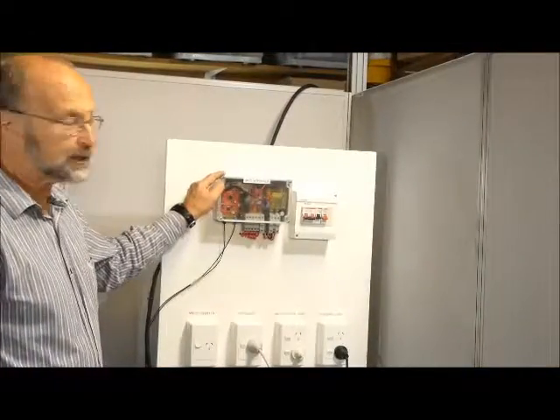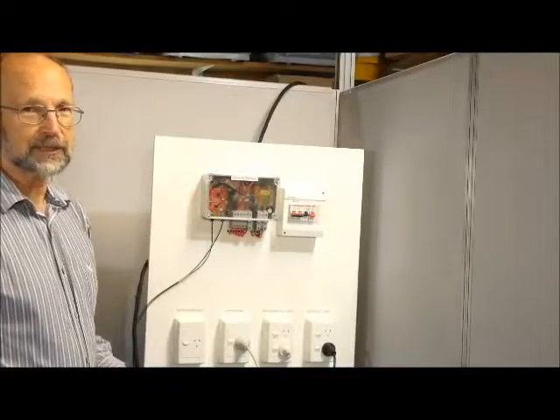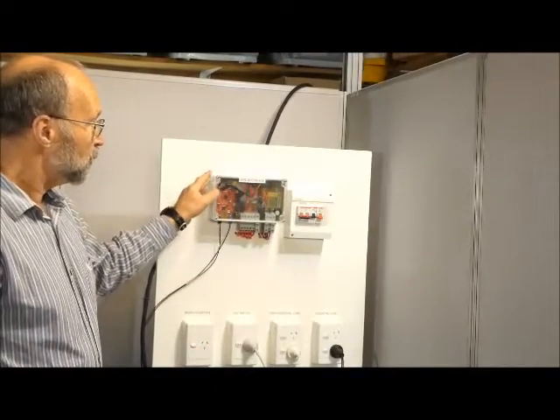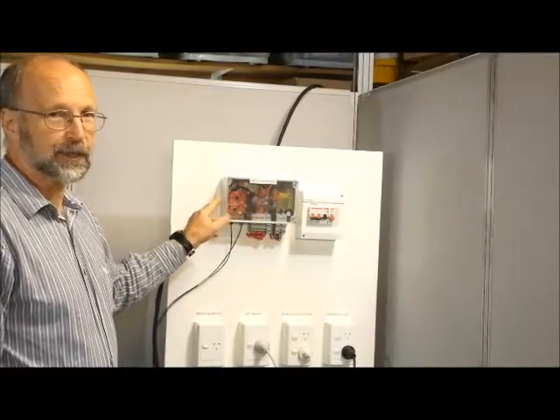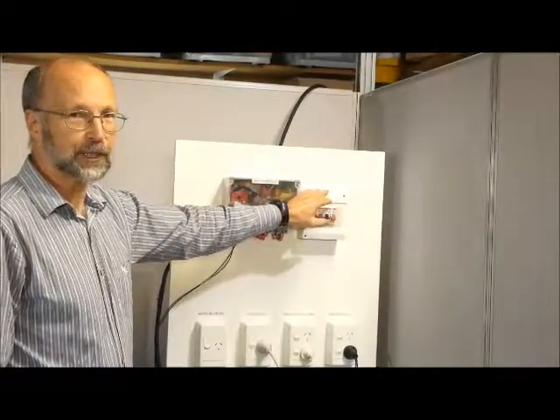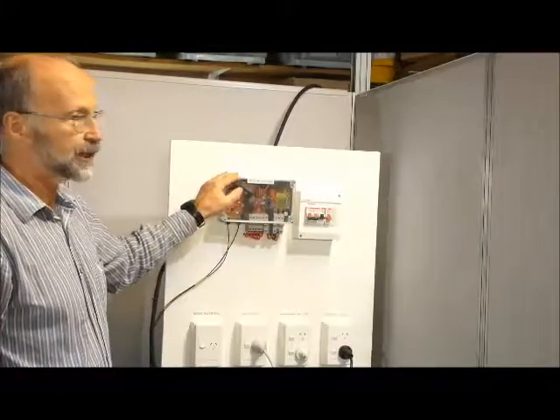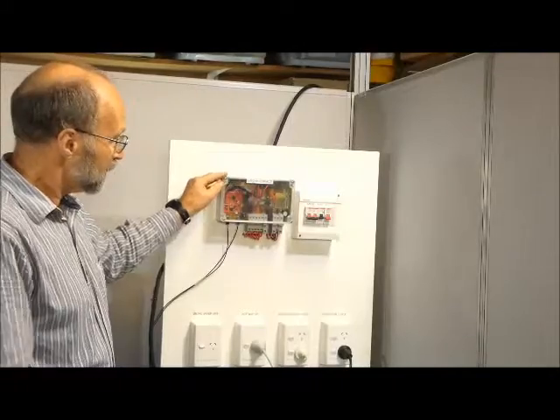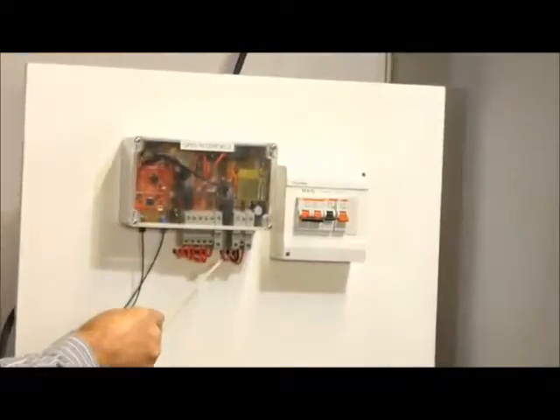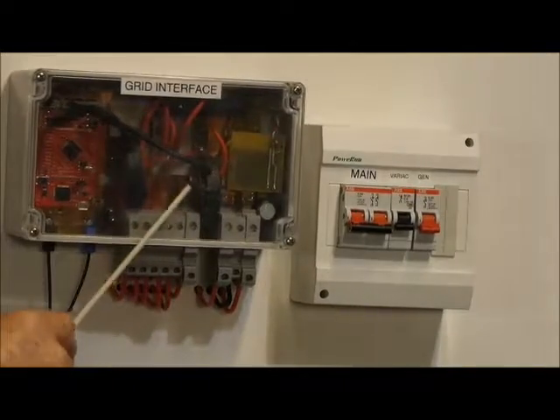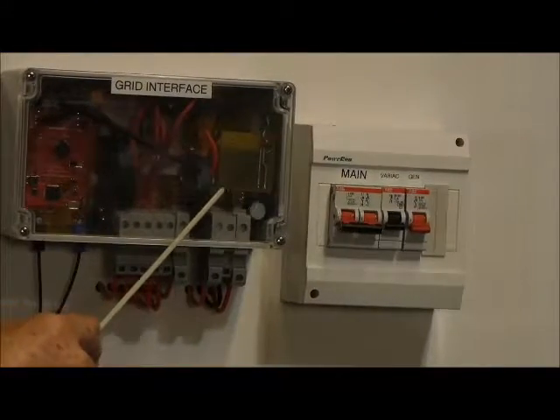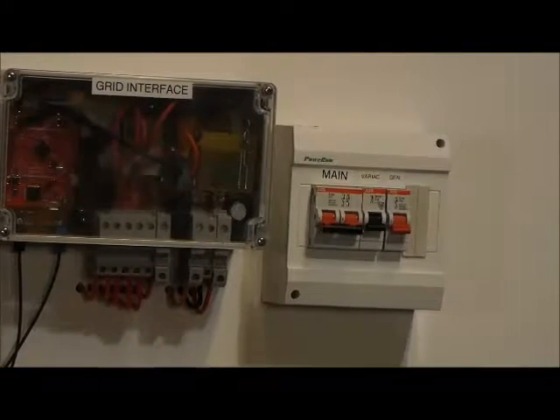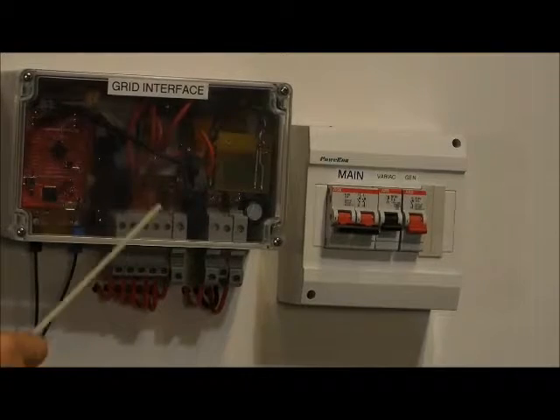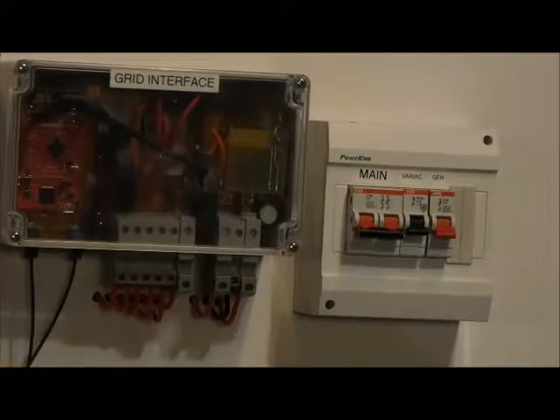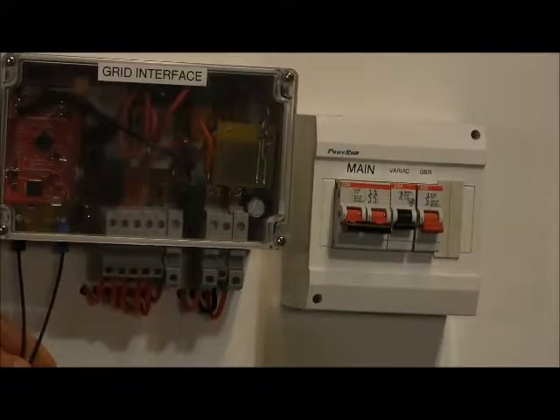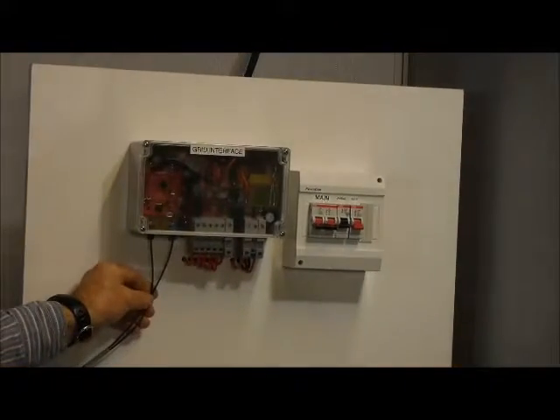This is the grid interface, which is the part of the system that makes it very easy to install. So all the current monitoring for current going in and out of the house is done close to the distribution board for the house. You don't have to take thick wires from here to the inverter and back again. Inside here we're running the main connection from the grid through a Rogowski coil to sense the current and back out to the distribution board. And also in here we're measuring grid voltage, and we have a phase lock loop which synchronizes up to the grid and then communicates the phase information to synchronize the inverter with the grid.